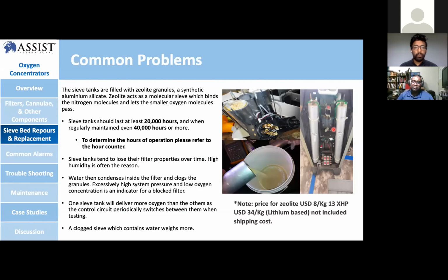So, a common problem: the zeolite always has a lifespan. For a zeolite sieve tank, it can last up to 20,000 hours. Some, if you maintain them very well, work up to 40,000 hours. So it depends how you maintain it. You keep it clean, and always make sure that you check the hour counter as a reference. Is it 20,000 hours, 40,000 hours, all that?